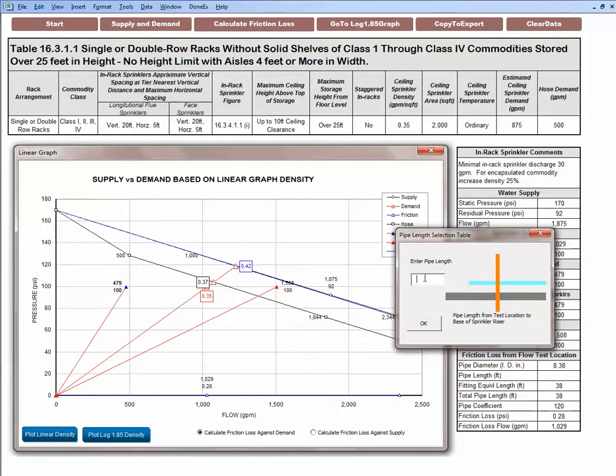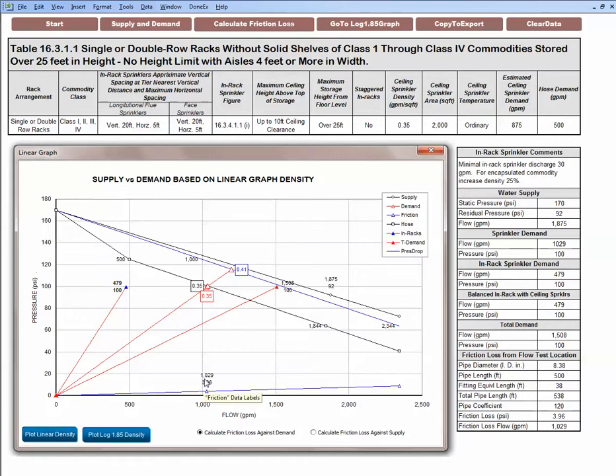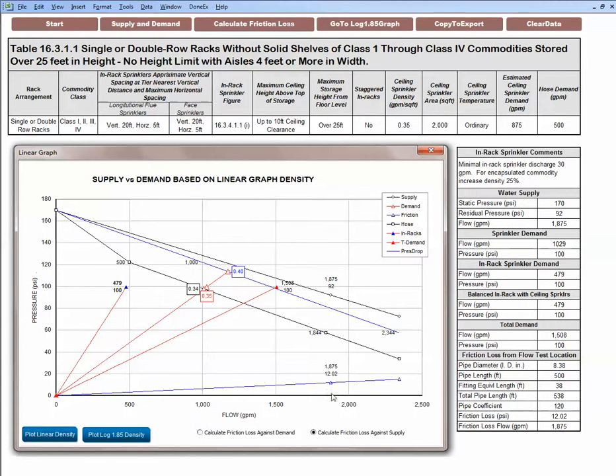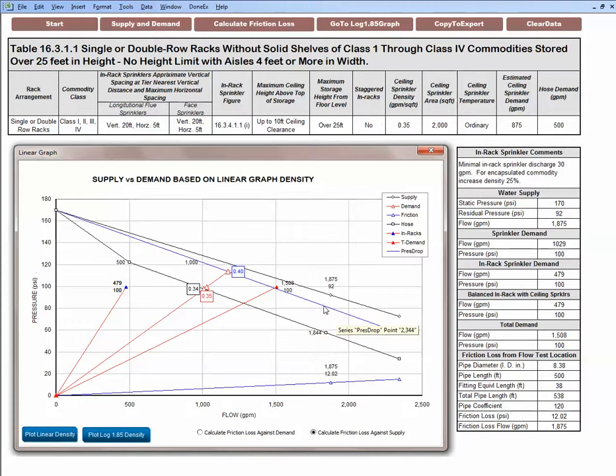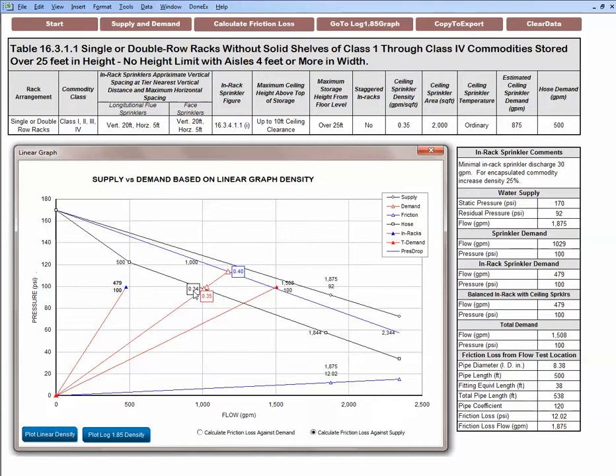We click OK and another window opens up where we enter the pipe length. Let's set 500 feet of pipe. The friction loss is generated based upon the sprinkler demand of 1029 gpm. Based upon the water supply you click this button and the friction loss increases. The friction loss line is automatically subtracted from the water supply to give you a pressure drop line and this is your hose demand subtracted from the pressure drop line. Now it gives you the density available with hose and density available without hose.